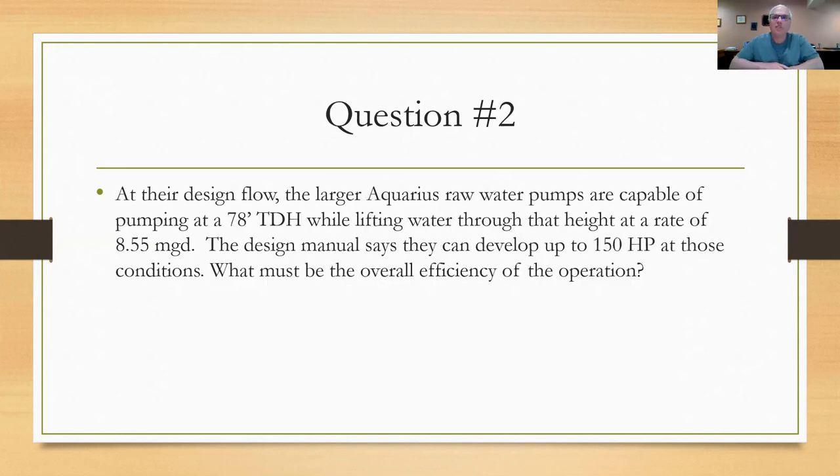This question is saying that at the design flow, the Aquarius water treatment plant has five pumps, five of them down there, that are capable of pumping at a head of 78 feet. When they lift water through that height, they're operating at a rate of 8.55 MGD. There are five pumps down there. Three of them are 8.55. There's two others that are smaller. So what they're saying is there's one of the big ones operating and it's developing 78 foot of total dynamic head. If the design manual says they can develop up to 150 horsepower at those conditions, what must the overall efficiency be of that operation? We know from a previous formula that we used in one of our hydraulic series that the horsepower equals gallons per minute times the feet of head divided by 3960 and the efficiency of the system. If you want to stop here and work that through, go ahead, stop the video. Otherwise, I'm going to move on here.